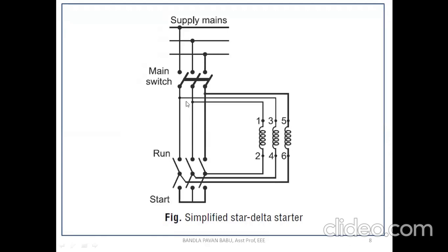Let us see. If we consider the R, Y, B phases, then for the R phase, between 1 and 2, through this it is connected. All these are shorted there, and it is connected to the neutral: 2, 4, 6 are shorted here, you can see. Whereas in the run position, 2, 4, 6 are not shorted; all these are separately connected. So 2, 4, 6 shorted and connected to neutral means a star connection. Other than that it is delta connected. Look here, 1, 2, again it is given to, and again some 5, 6, so this is the connection.